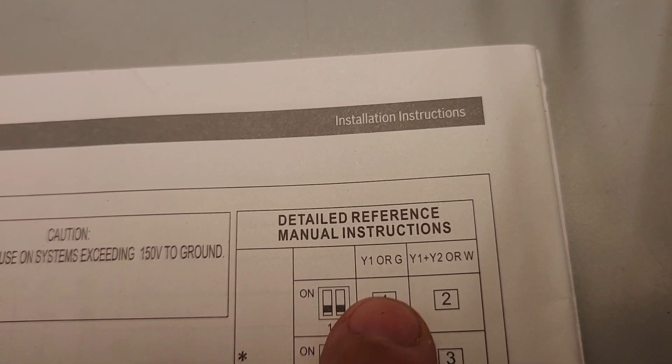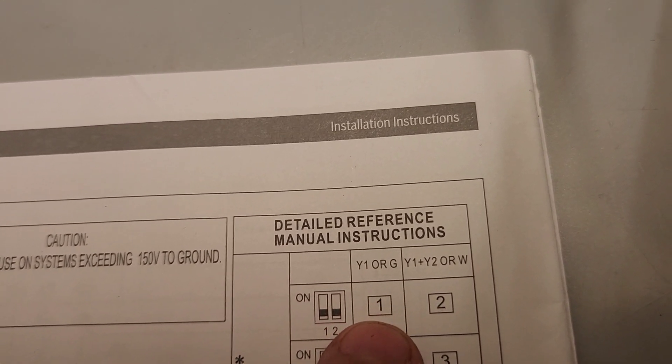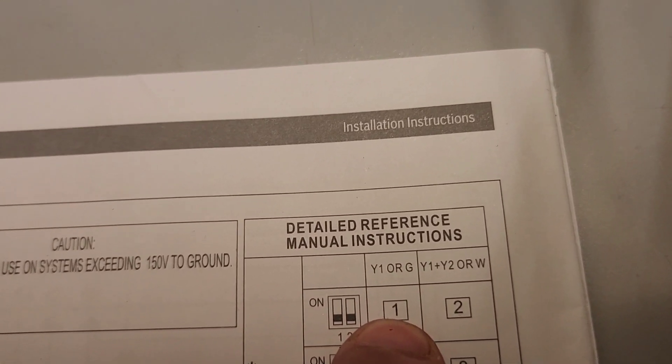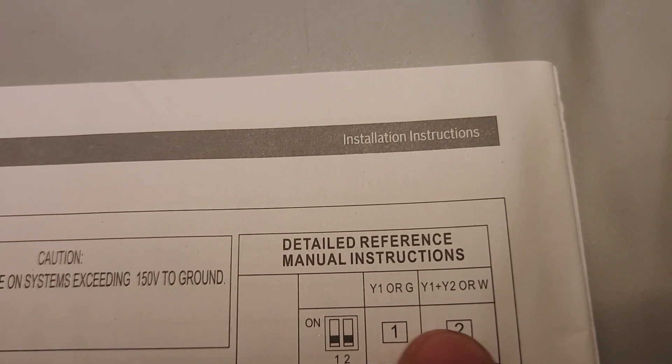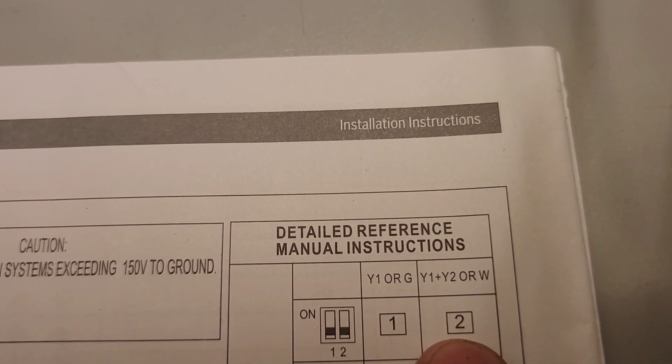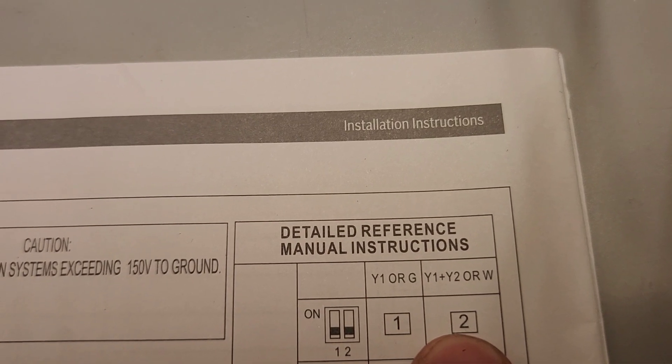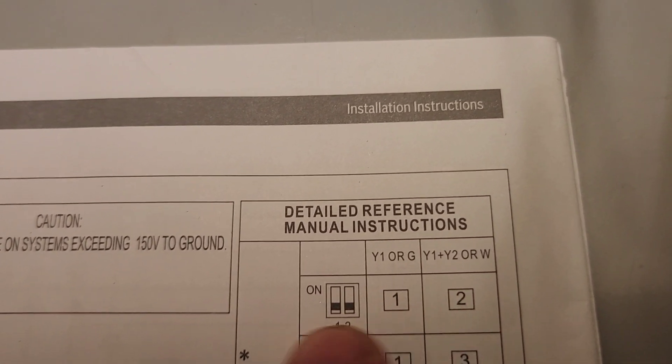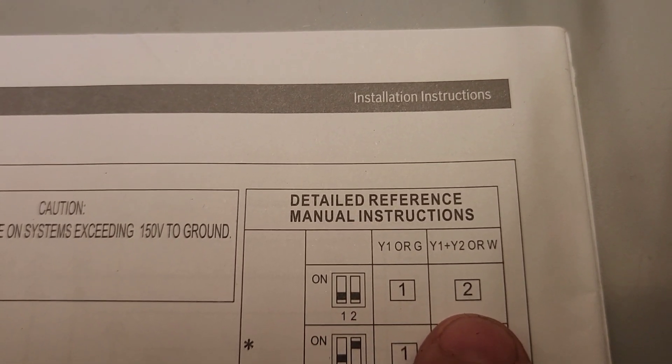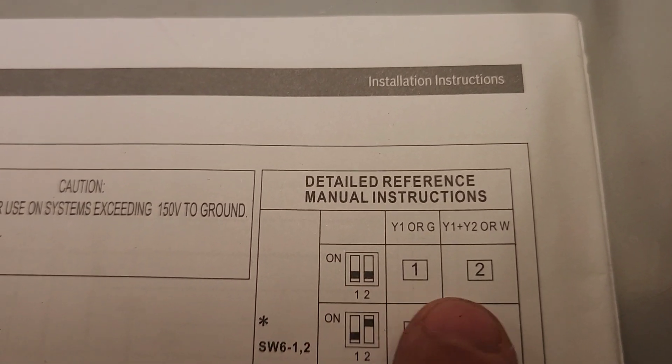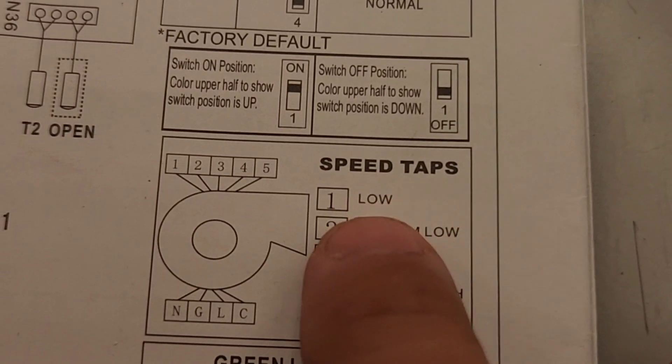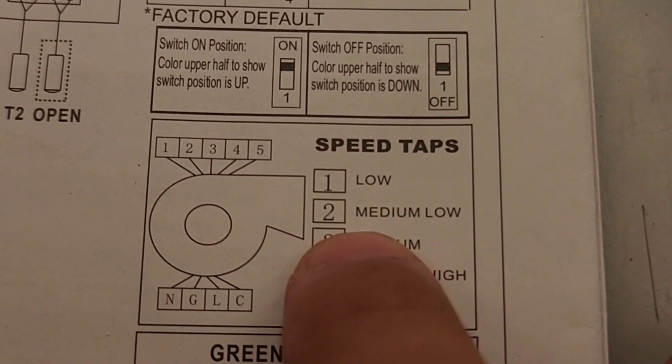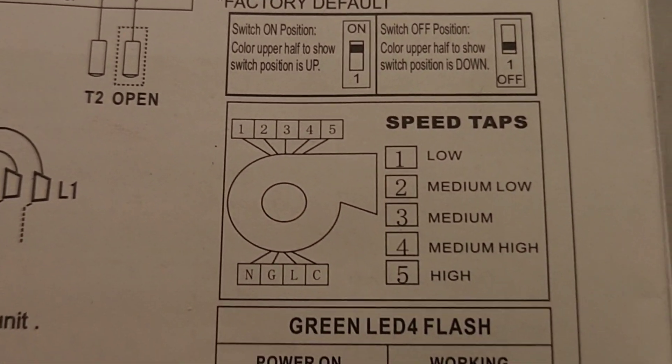So what this is telling us is that when we're getting only Y1 or a G call, we're running a speed number one. When we're getting a Y2 or a W call, this is going to run a higher fan speed, and that's going to get speed number two. Well again, that still doesn't tell us what CFMs we're running. Now let's go to the next step. As you can see, speed tap one is considered low, speed tap two is considered medium low.